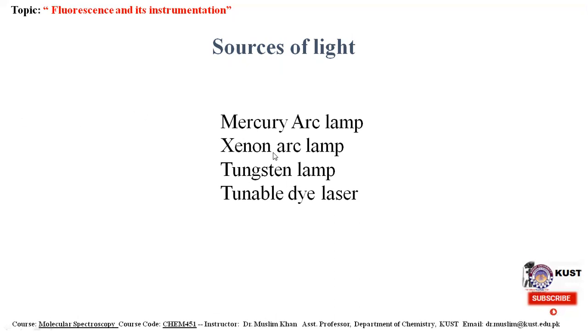The xenon lamp is used in the UV visible region. Tungsten and tungsten halogen lamps are used in the visible region. Similarly, the mercury lamp is used for emission lines, and it occurs in the range of 250 to 800 nanometer. The other lines are 365, 394, etc.